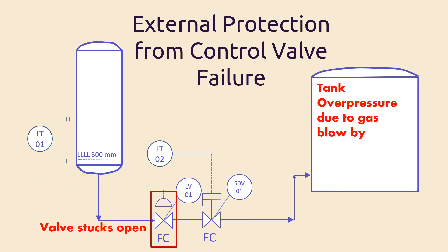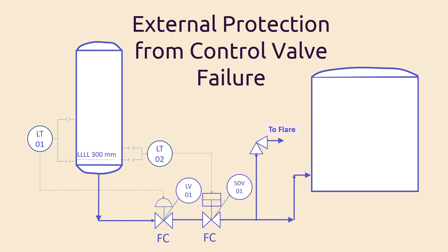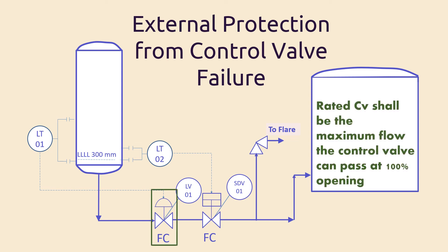Depending on the criticality of the overpressure consequences and the reliability of the instruments or the emergency shutdown system — which is usually studied in HAZOP and SIL analyses — we may need another layer of protection. There is a higher level of protection to protect the system from control valve failure, which is to install a PRV (pressure relief valve) for liquid services, or a PSV (pressure safety valve) for gas services. The safety valve shall be set at a certain pressure, and once it reaches that pressure, it shall open and the pressurized fluid is either sent to flare for gases, or to another downstream system for liquids. So if we need a PSV in our case where the overpressure will be due to gas flowing to the tank, we shall send the gas to the flare. The PSV shall be sized to handle the flow rate when the valve is at its rated Cv.